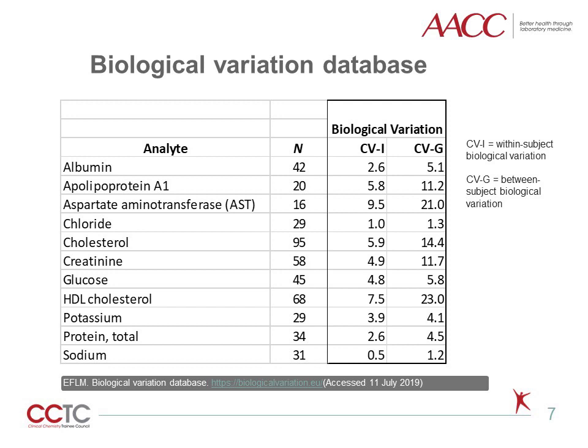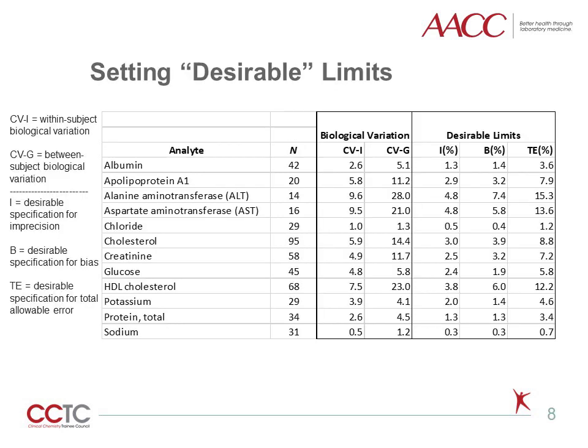The most recent biological variation estimates and database are provided online by the European Federation of Clinical Chemistry and Laboratory Medicine, or EFLM. The EFLM provides a meta-analysis of published papers on biological variation to obtain CVI and CVG estimates. The table in this slide was created for selected chemistry analytes using median values for CVI and CVG from the EFLM website, along with the number of publications used to generate the final estimates. These numbers will be used to set analytical quality goals, expanded to include desirable limits for imprecision (I), bias (B), and total error (TE), all expressed as percentage values.